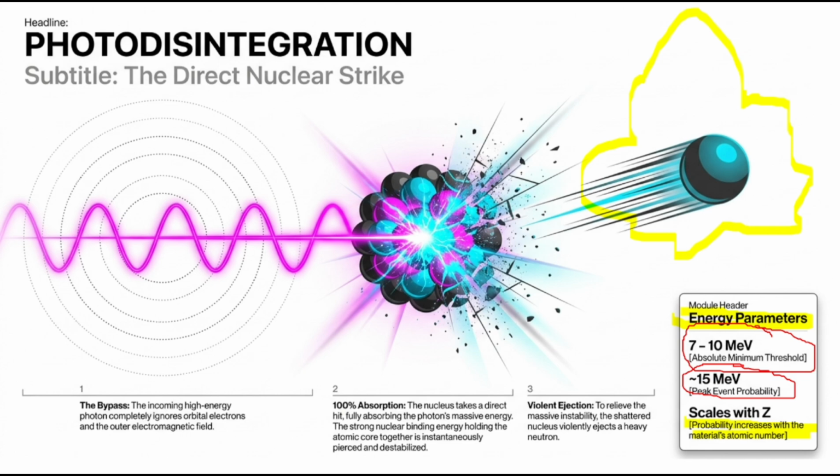This is why your radiotherapy bunkers require extensive shielding. You must use highly specialized hydrogen-rich shielding. Materials like polyethylene or specialized concrete are used to successfully slow down and absorb these deadly neutrons.